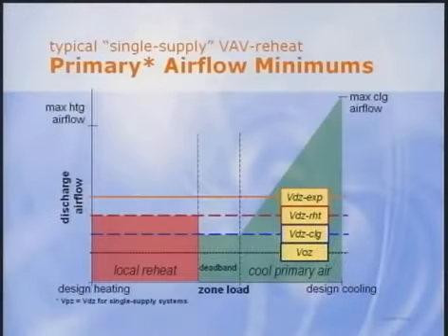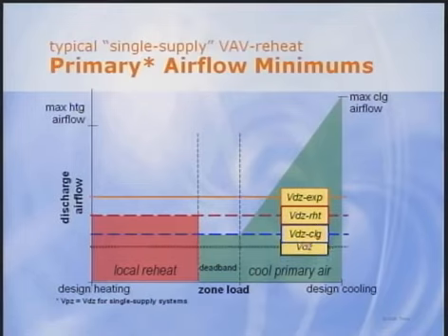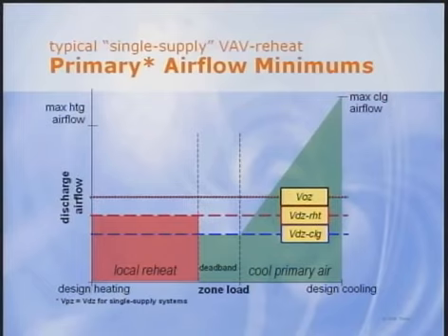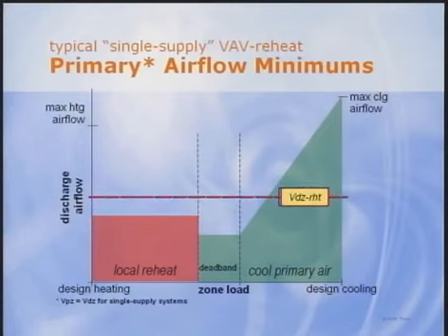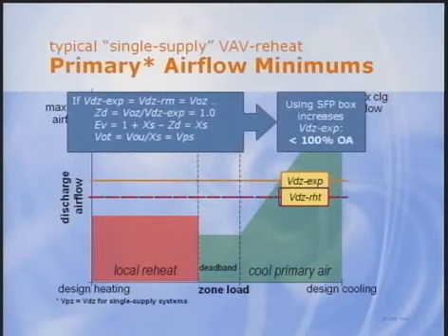Whatever approach is used, the requirements in the two standards don't conflict, but that doesn't mean it's always easy to comply. In some cases, it might be necessary to adjust system configuration. For example, Standard 62 might require a very high outdoor airflow for an interior conference room. Although Standard 90.1 allows designers to raise the reheat minimum setting to equal it, this forces 100% outdoor air at the intake. For zones like this, designers might use a series fan-powered box to raise the minimum expected airflow without actually raising the minimum settings.